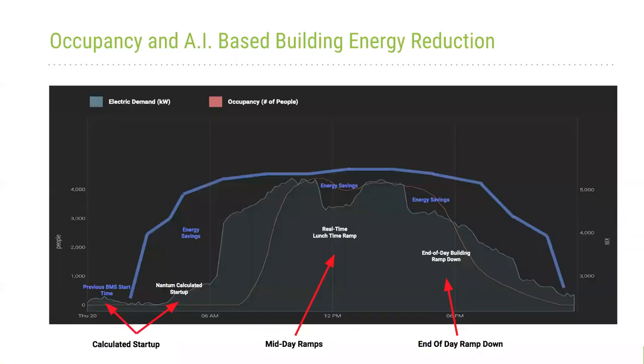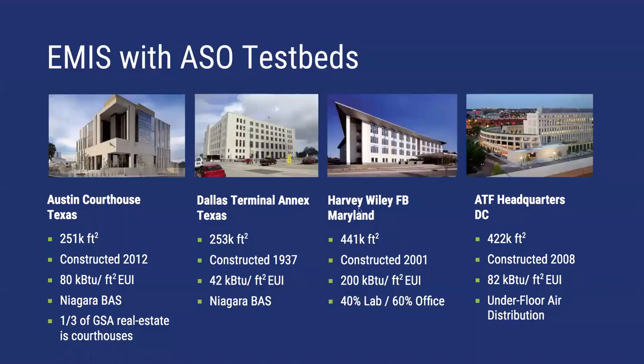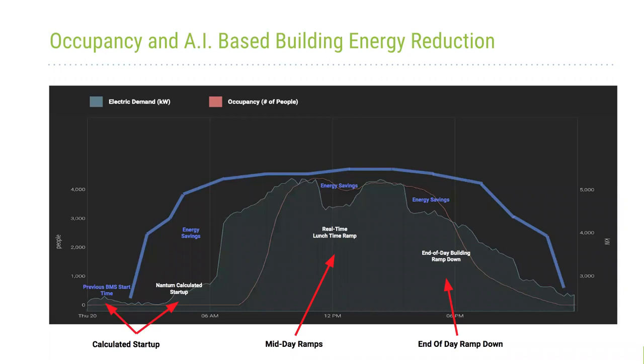The EMIS with ASO was used to identify and implement optimum start time for air handling units based on interior and exterior conditions and historical data, as well as mid and end of day ramps based on occupancy. In this sample figure, we see a sample base load, the business-as-usual case, indicated by the thick blue line, and the calculated optimum air handling unit start time and mid/end of day ramps, indicated by the red arrows. The resulting energy savings is reflected by the area between the thick blue baseload line and the optimized load, shown as the thin teal line.